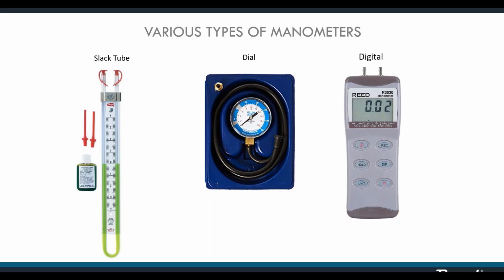They are considerably more expensive, but they measure in much smaller increments. As you can see, this one measures down to 1/100th of an inch water column. A far smaller increment than you would need on a device of this nature. Choose the one that you find appropriate. They should all come with tubing to complete the distance from the test port to the manometer and a fitting to adapt the hose to the test port.